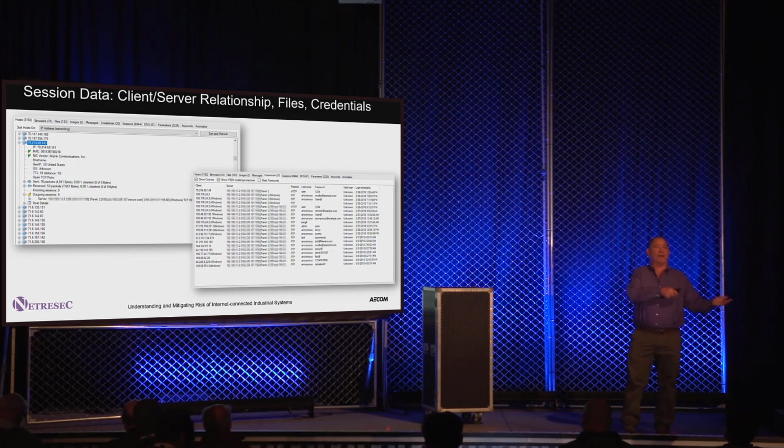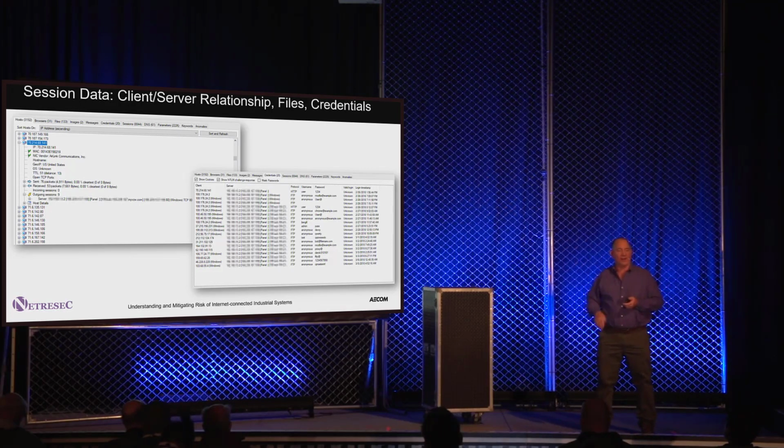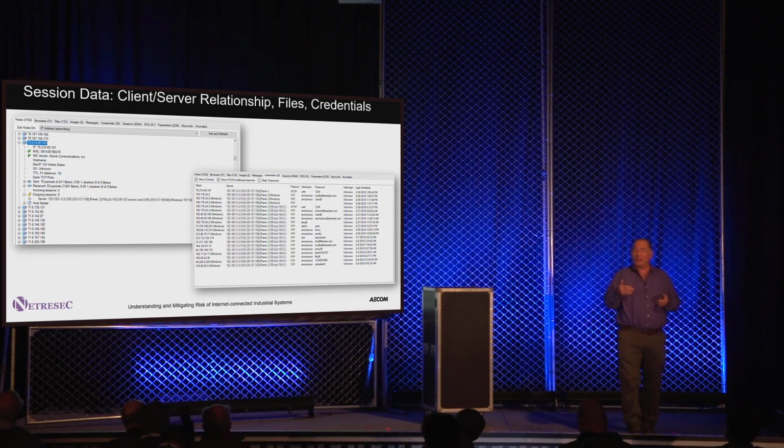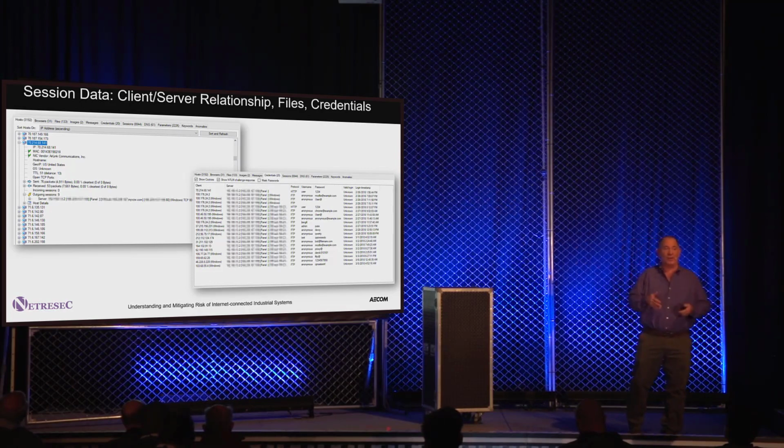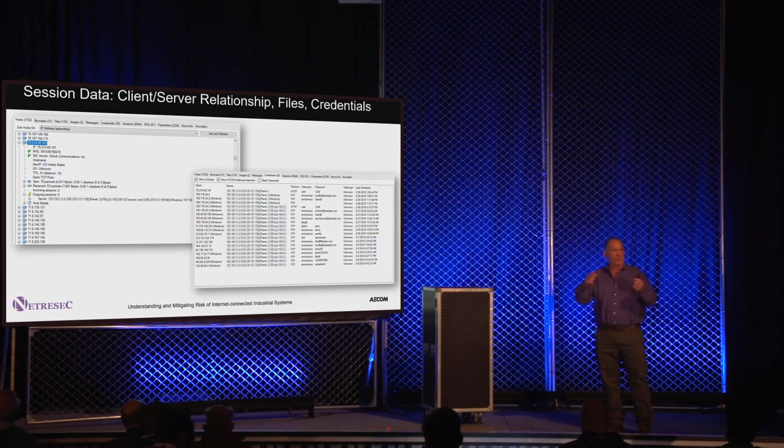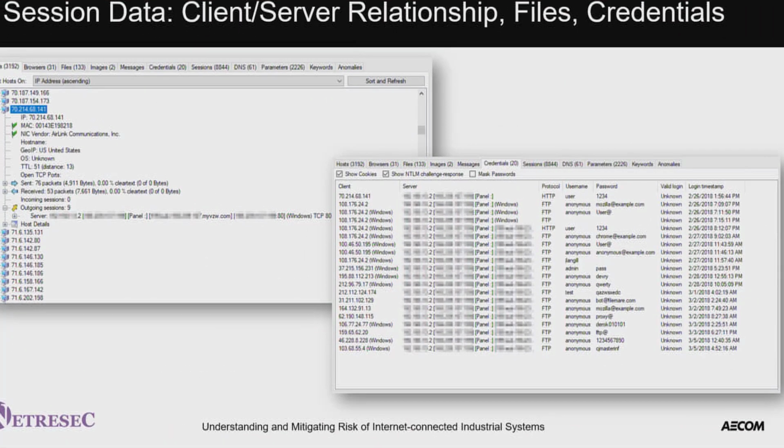Okay, so once you log into the panel, it goes from a read-only view to a read-write view. Defaults. So, of course, that's not Automation Direct's problem. It's the integrator, this company that sells this awesome package where they say they've got all these neat, slick features, and of course, one of them is a very secure remote access solution. It's not very secure.